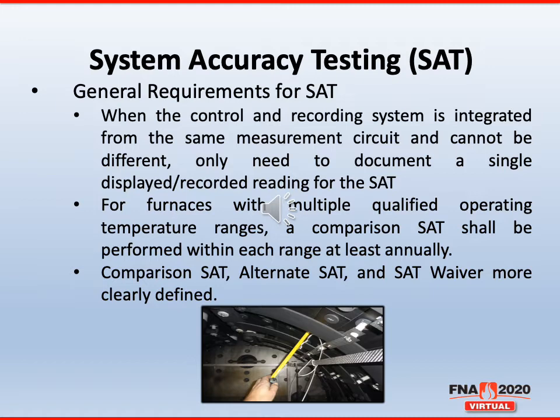Again, these would be for those advanced systems such as a PLC control or Honeywell HC900 or a Yokogawa control data acquisition system as one, since it's the same circuit just displayed two different ways as a control and recording sensor. When you do conduct an SAT, only one value is required to be recorded. We also addressed furnaces with multiple qualified operating temperature ranges.